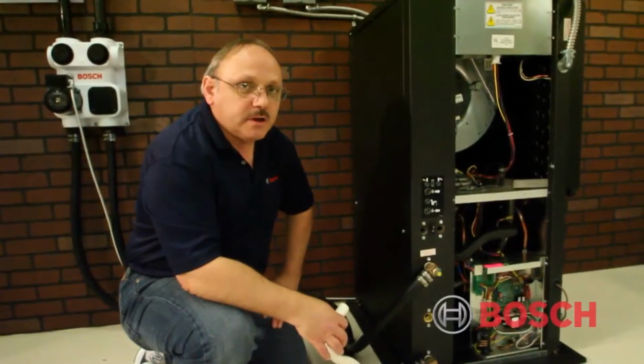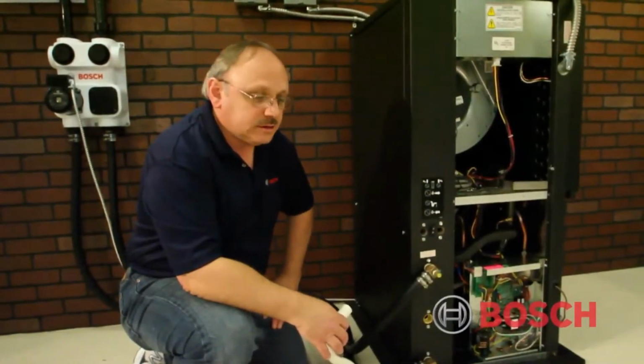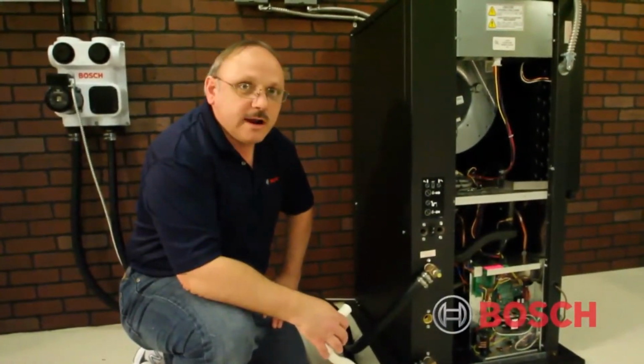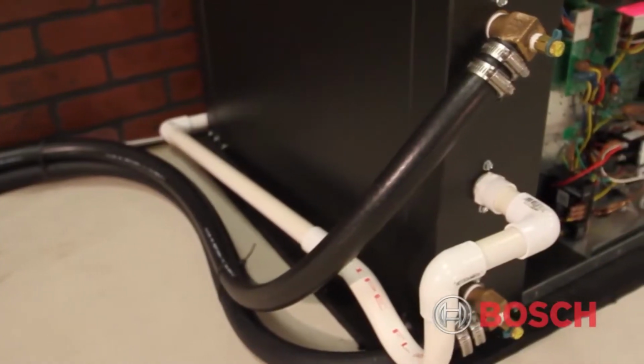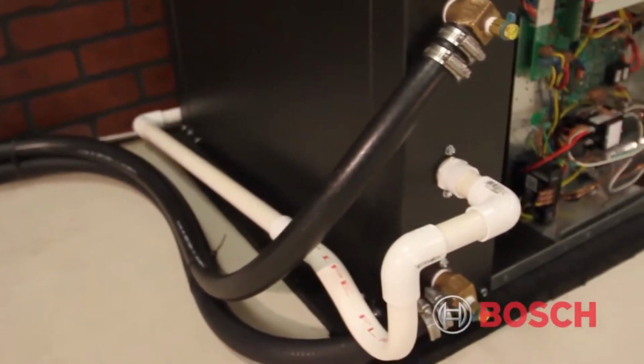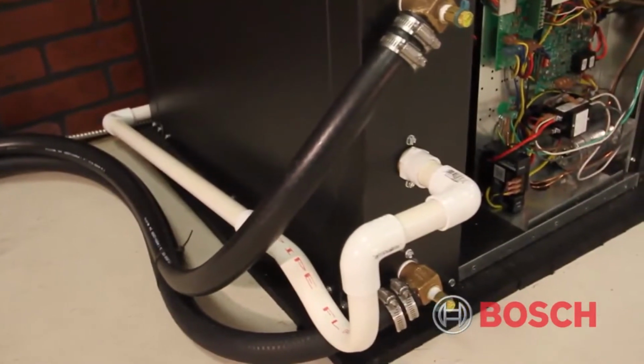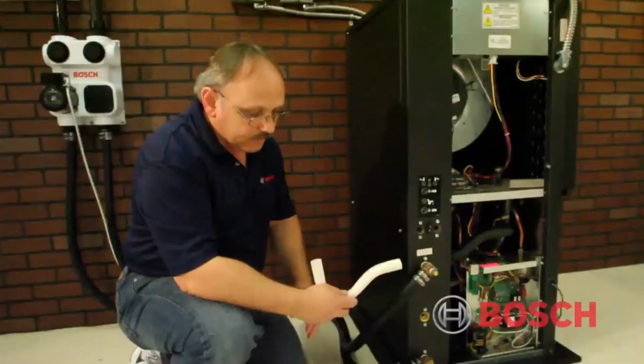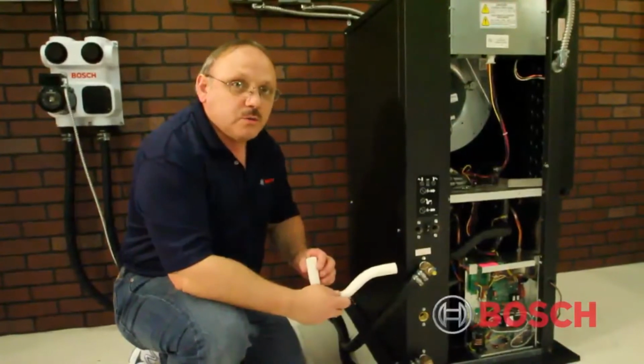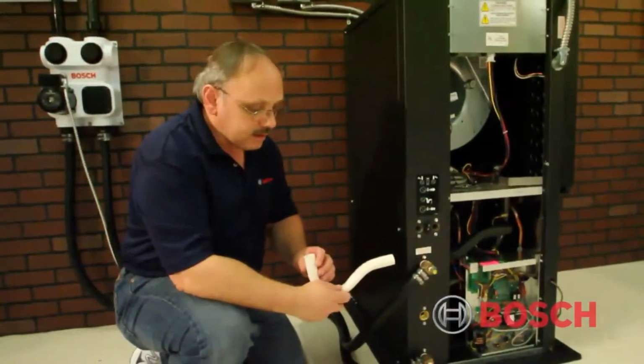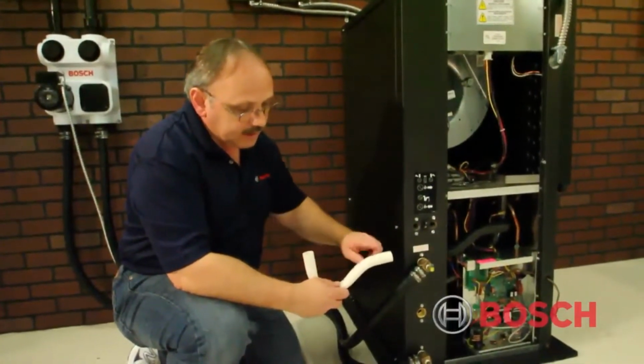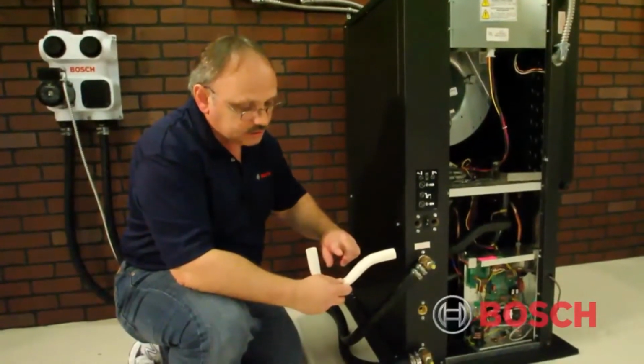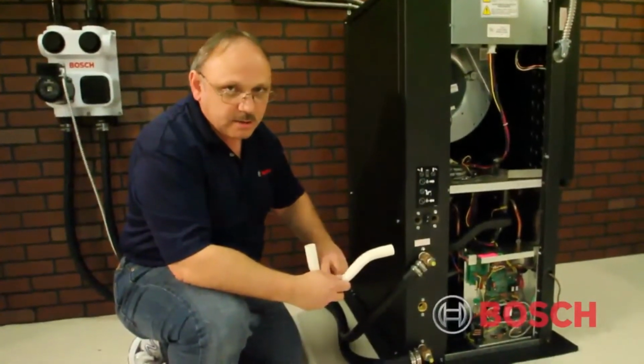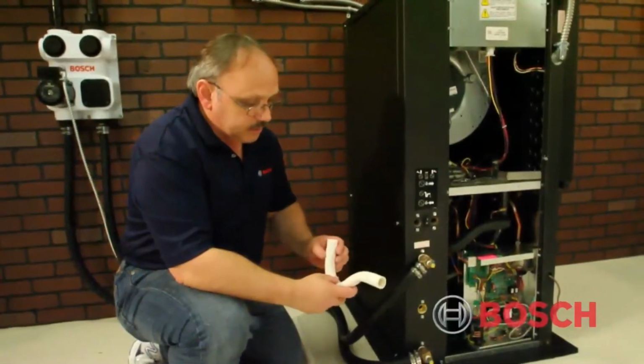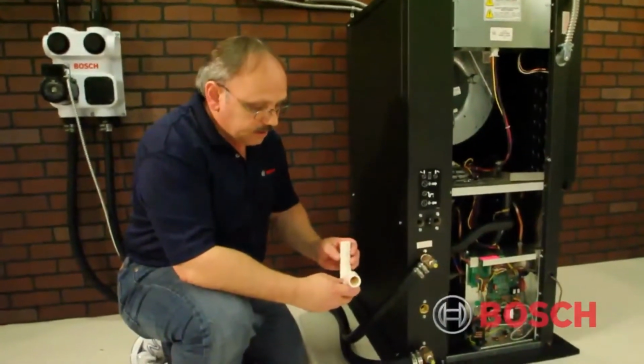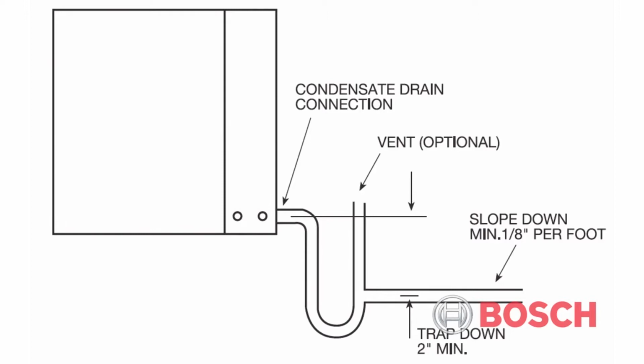Next thing I'm going to do is pipe up the condensate drain. All of the units that we produce are going to require a trap on the drain outlet, so make sure you select a trap that is deep enough to overcome any static pressure that could be caused by the blower. Typically on variable speed models, you want something that is at least 2 inches in depth from your outlet to the outlet of your trap, and then another additional 2 inches from the outlet of your trap to the bottom of the trap. So make sure you select the proper trap for the application, and also make sure you follow your local codes and how you pipe these up.